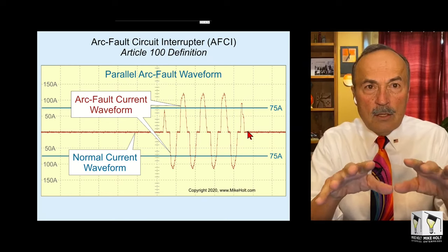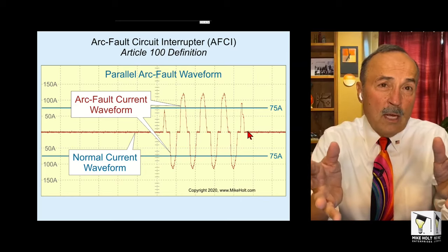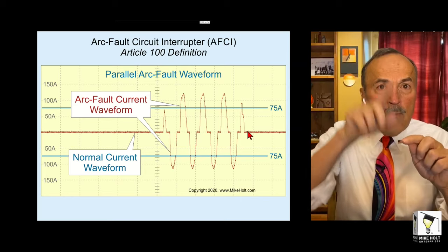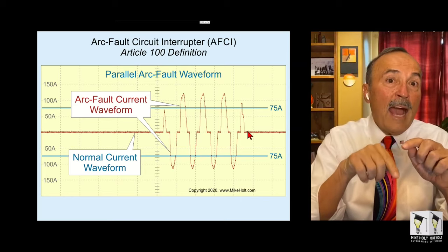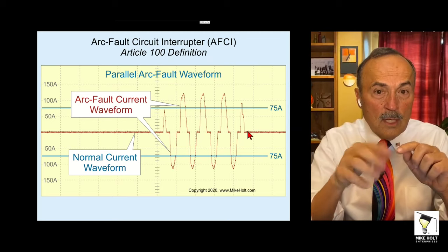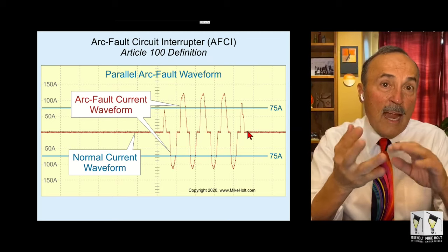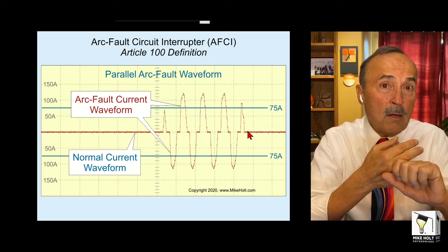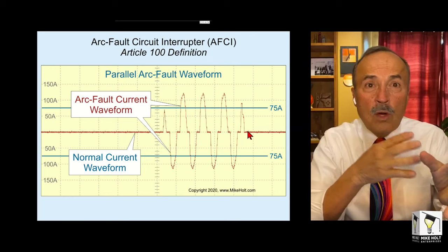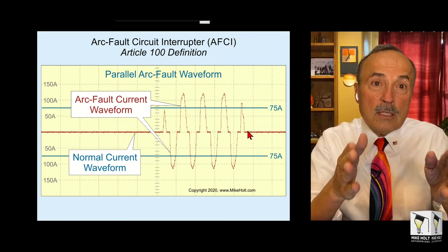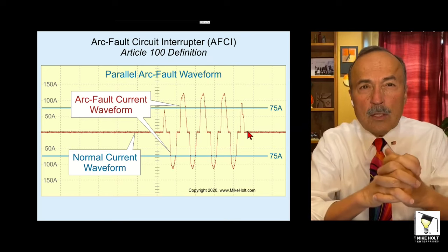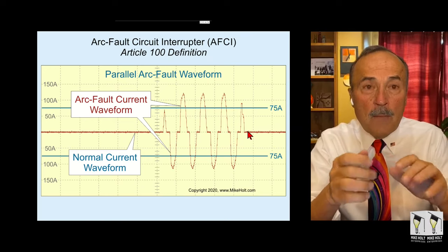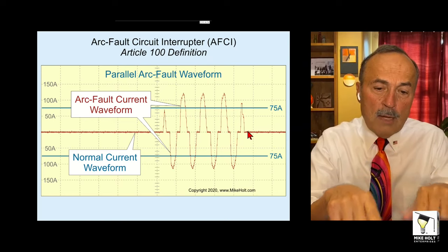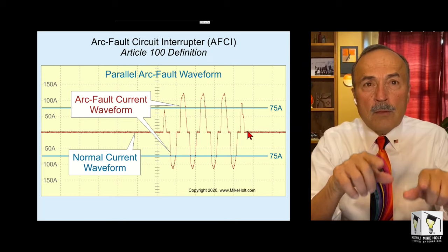Now, in the standard, which I don't need to get into, and I don't remember what they are, it counts the number of half cycle waveforms that are over 75 amperes that have the characteristic of a parallel arcing fault. And once it gets that number within a given period of time, then it says, okay, clearly it's an arcing fault. Then it opens. Now, there's another, I need to get it. Brian, remind me to get a graphic in here.